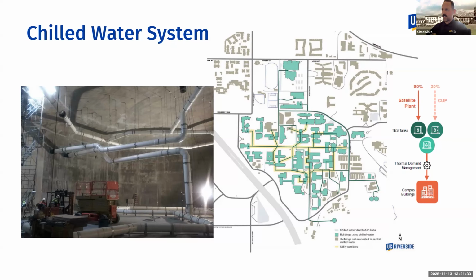And then a decade later, in 2013, TES-3 was finally installed adjacent to number 2, and the satellite plant received its 3rd duplex chiller and tower. So TES-3 is slightly smaller at 2.2 million gallons and has a 20,000 ton-hour capacity. It wasn't until 2016, as I mentioned earlier, that RPU implemented time-of-use rate structures, and demand charges appeared on the bill for the first time. That was a $60K hit they took on that bill that I looked at. And yeah, they were like, what do we do now?